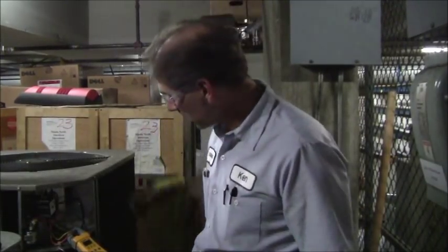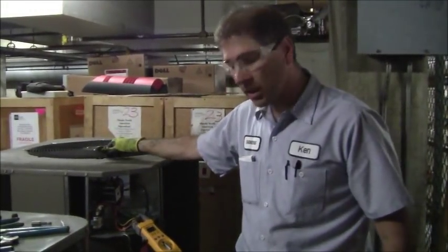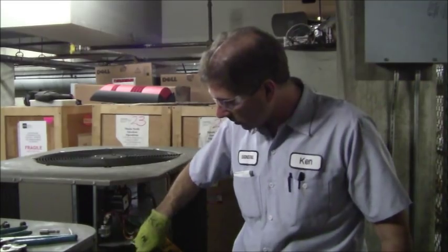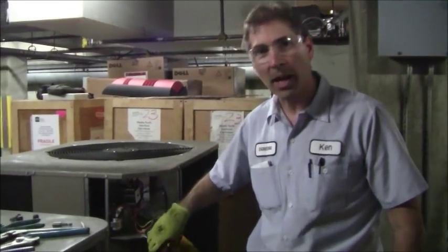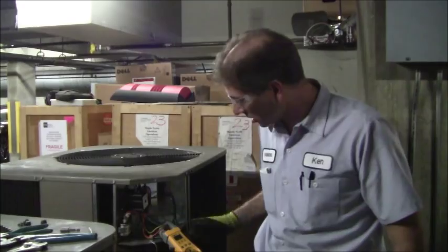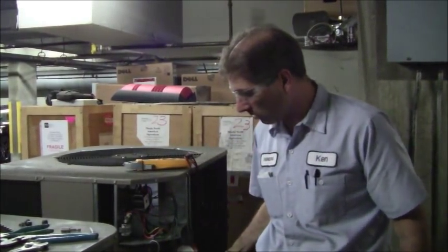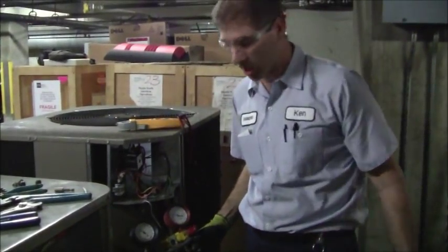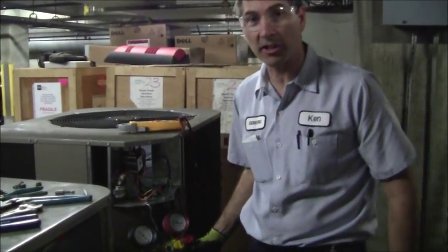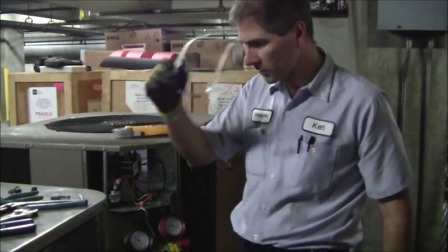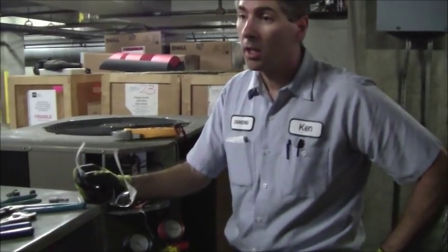Alright, so basically, either way, I was just trying to demonstrate a compressor with mechanical damage. I don't know if you saw the gauges, but I wasn't seeing any pressures on the gauges. It wasn't giving me normal readings on the gauges at all. So this compressor definitely has some type of internal damage to it. And there's not much I can do except replace the compressor.